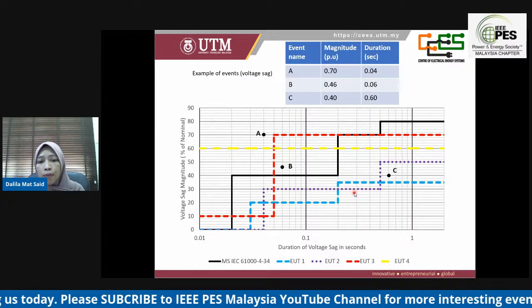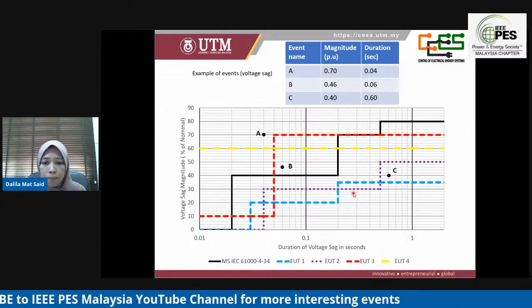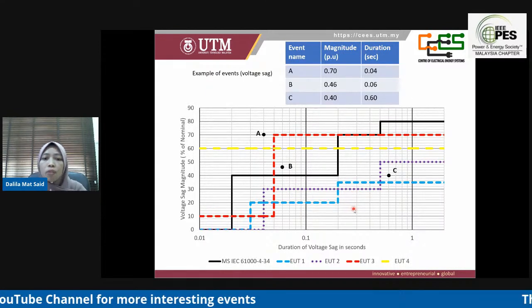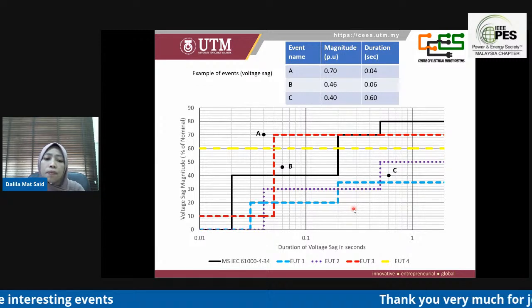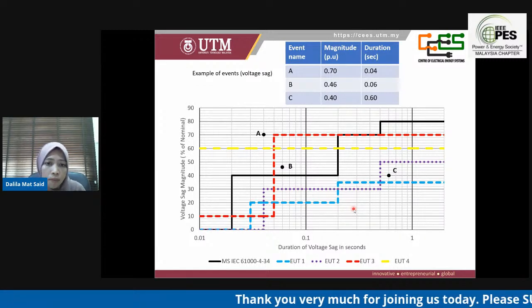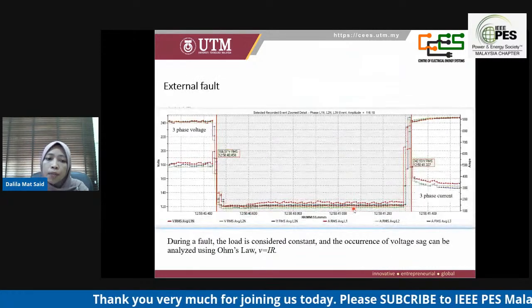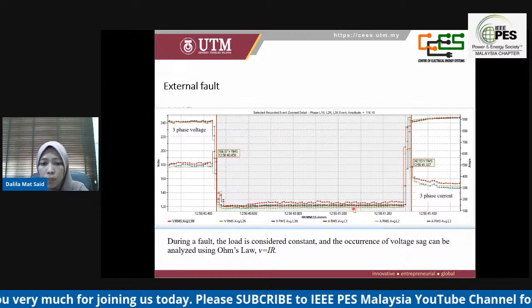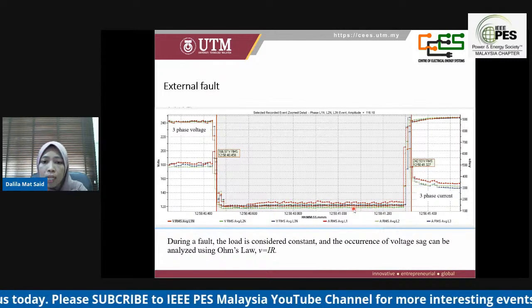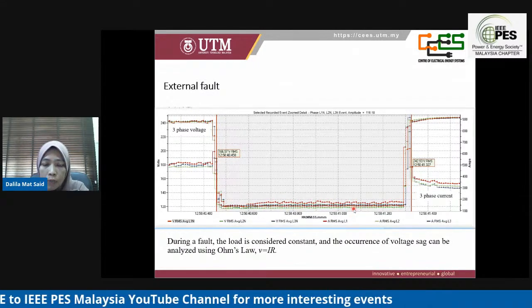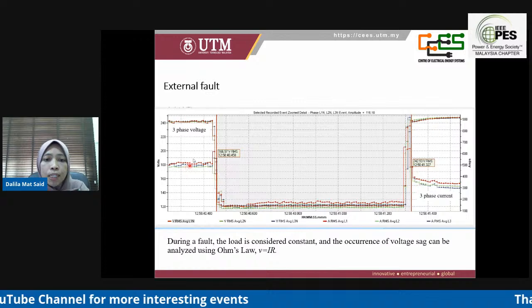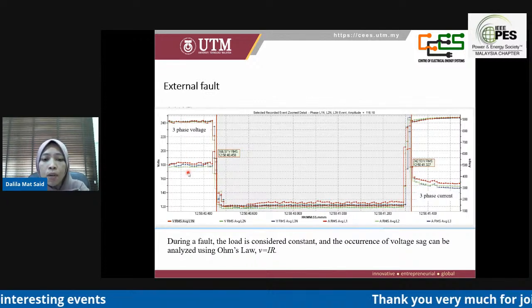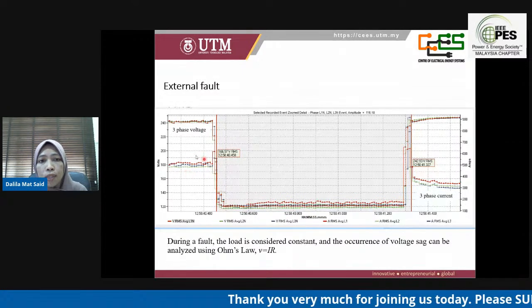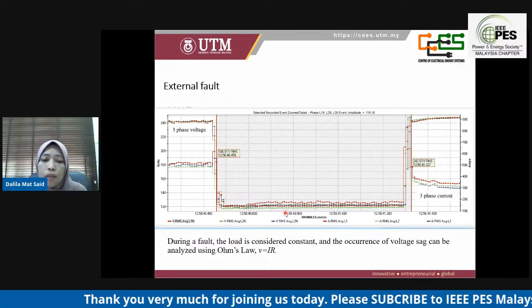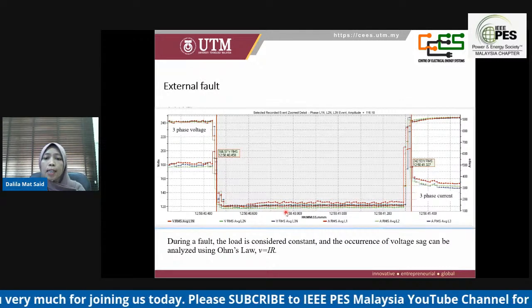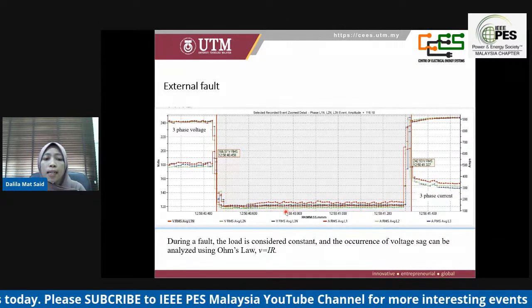Okay, after we have found the problem and seen the impact of the event, as a user, of course, we want to know where the source comes from, either internal or external. So we refer to this graph, which we will obtain through the monitoring process. When you capture the event, the graph shows the three-phase voltage and also the three-phase current. For an external fault, if the voltage drops, the current also drops. We can observe this data from the recorder, and the concept is that during a fault, the load is considered constant.